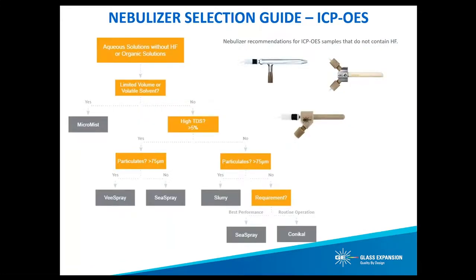This first flowchart summarizes various nebulizer recommendations for ICP-OES samples that do not contain hydrofluoric acid. It's not recommended that a glass or quartz nebulizer be used with any amount of hydrofluoric acid. The particular nebulizer selected should also closely match the desired sample uptake rate. You can visit the Glass Expansion website geicp.com for a complete listing of each nebulizer model and the available uptake rates. For any concentration of total dissolved solids greater than 1%, we recommend the use of an argon humidifier for optimum nebulizer performance and long-term stability.